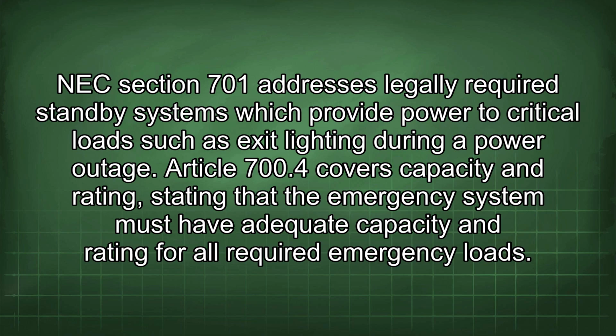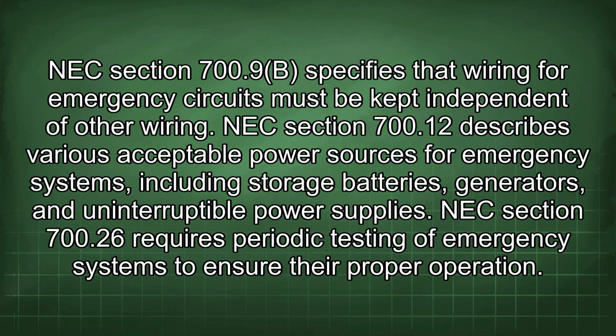Article 700.4 covers capacity and rating, stating that the emergency system must have adequate capacity and rating for all required emergency loads. NEC Section 700.9b specifies that wiring for emergency circuits must be kept independent of other wiring. NEC Section 700.12 describes various acceptable power sources for emergency systems, including storage batteries, generators, and uninterruptible power supplies.